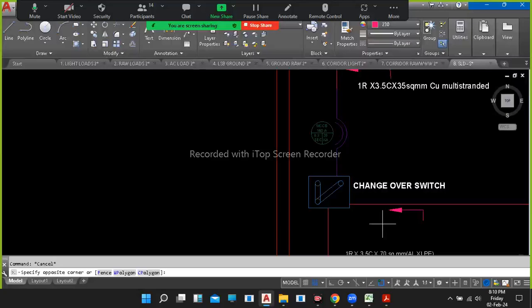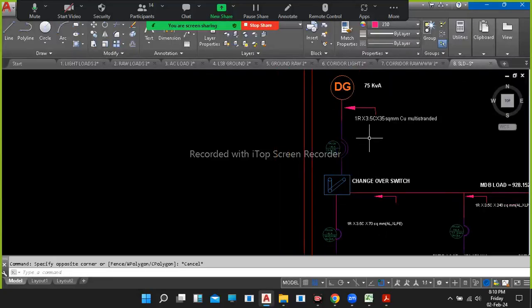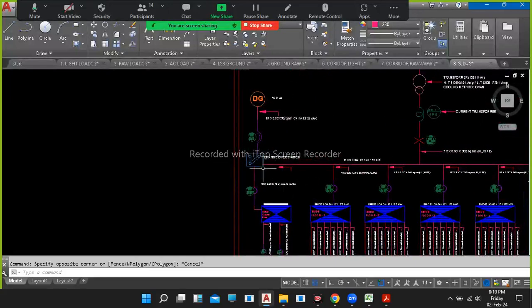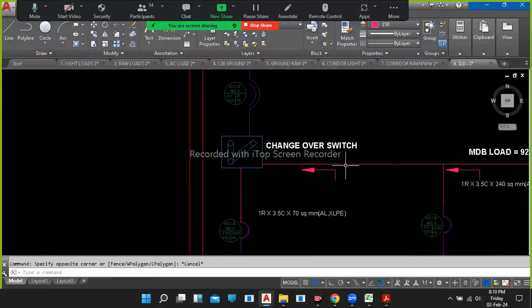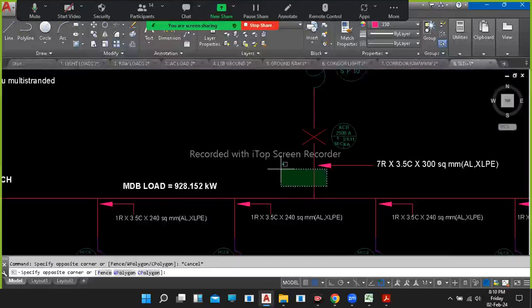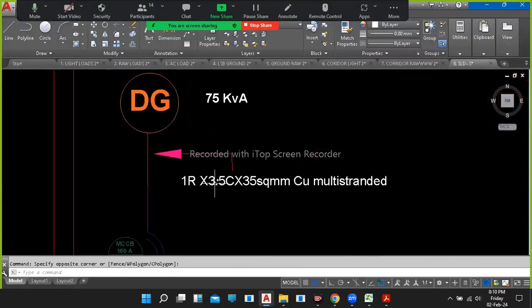So that when main power is there, main power will come like this and it will go. When the main power is not there, the generator has to be switched on, and the generator power will be going. But if the client says that I want the generator to be provided for the total building, we'll remove this changeover and we'll place the changeover here. Because at that time, based upon the MDB load, we are going to calculate the generator size. Okay, so there the changeover will be provided, and according to this, we'll be calculating the generator size and the cable size. Now adding up all this, we got the MDB load.